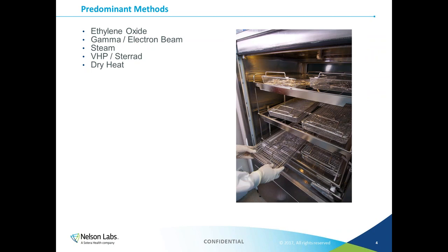Here is a brief list of the most common types of sterilization, generally sorted from most to least prevalent. Ethylene oxide accounts for greater than half of sterilization, followed by gamma radiation and electron beam, and finally steam. VHP, or vaporized hydrogen peroxide, is also common but less so than the others. Dry heat is generally used for terminal sterilization of products. We will go into further detail on EO, ionizing radiation, and steam, as well as what the designer needs to take into account for a successful design. Other types such as ozone, peracetic acid, and UV light exist but are not as commonly seen in the industry.